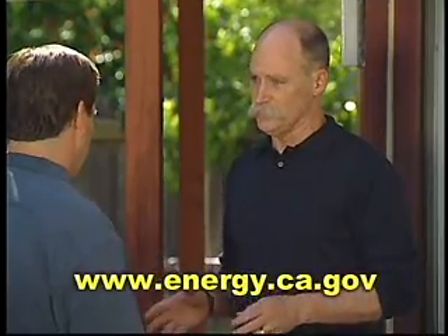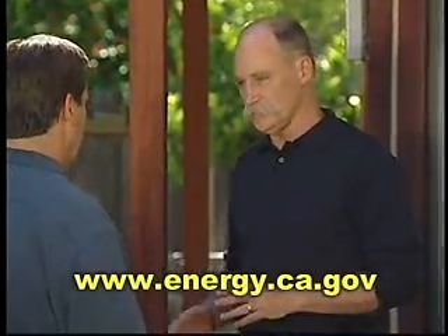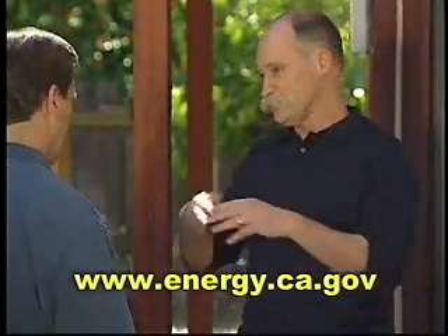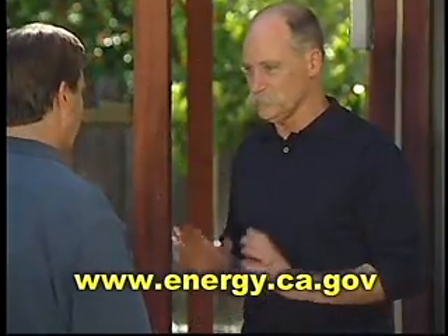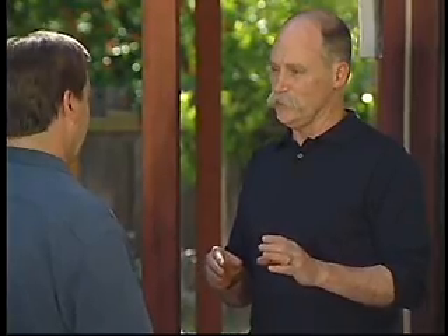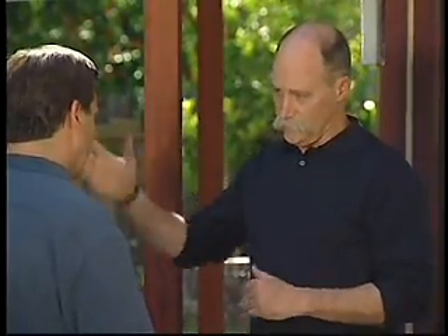Where do you go to find that information out? You compare it to a table which you can get at the CEC website. It's good for all the states, it's good for any place. It's good for Saudi Arabia, it's good for the East Coast, you name it. So you go on the website, you see what the amount of temperature split should be, and if your temperature split is too high, then you've got too low airflow.